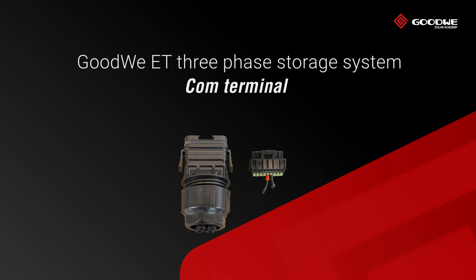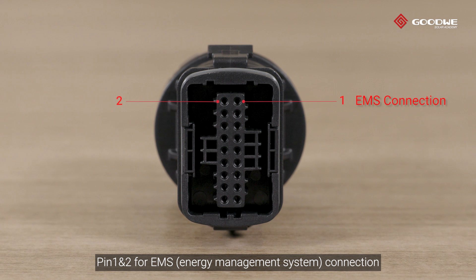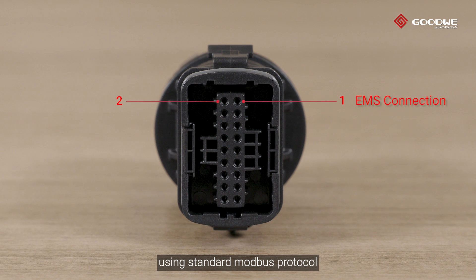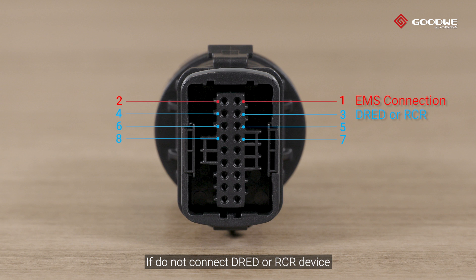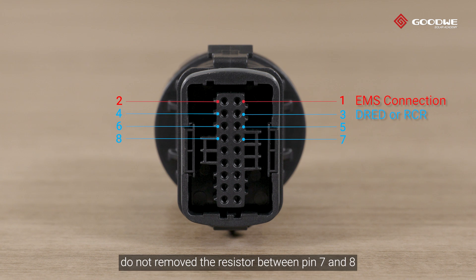COM terminal: Pin 1 and 2 are for EMS connection using standard Modbus protocol. Pins 3 to 8 are for DRED device and RCR device. If you do not connect a DRED or RCR device, do not remove the resistor between pin 7 and 8.